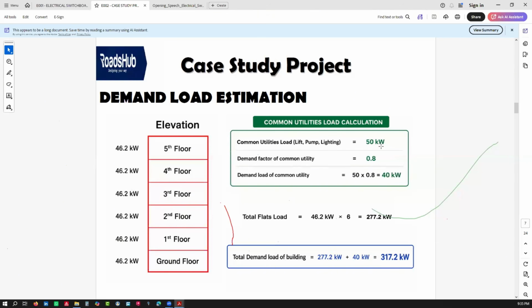Let's say, just as an example to reduce the calculations and a lot of details, you have 50 kilowatts for your common utilities. So you will use a demand factor of 0.8. Remember, the one for domestic houses is 0.7. For utilities and common services, we have industrial-like systems, so we go to a different value of demand factor. So you multiply 50 by 0.8, you get 40. Now you can know the total amount of power in the entire building by adding the floor values. How many floors do we have? 6. How much power per floor? 46.2. The total demand for the entire building will be the summation of the demand load for the utility plus the total demand load for your houses. You get 317.2 kilowatts.